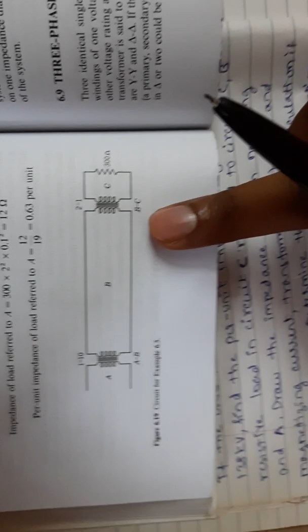If the base of the circuit is chosen as 10,000 kVA, 138 kV, find the per unit impedance of a 300 ohm resistive load in circuit C. Refer to circuits B, C and A. Draw the impedance diagram neglecting magnetizing current, transformer resistance and line impedance. Determine the voltage regulation if the voltage at the load is 66 kV, with the assumption that the voltage input of circuit A remains constant.